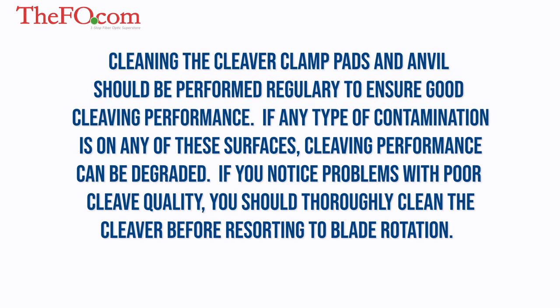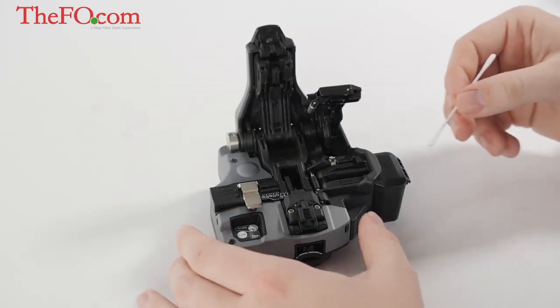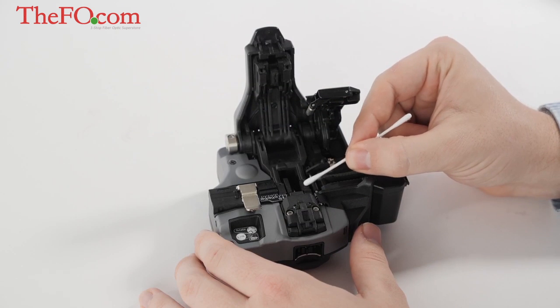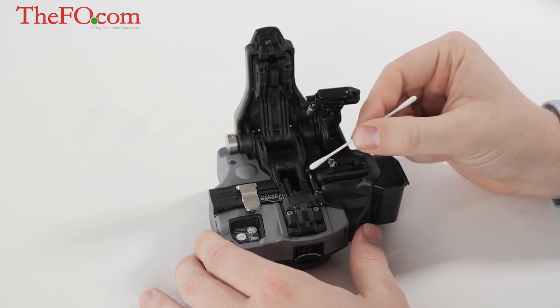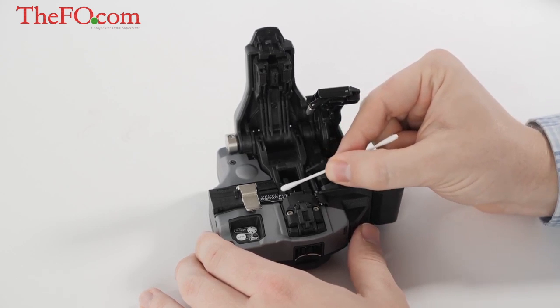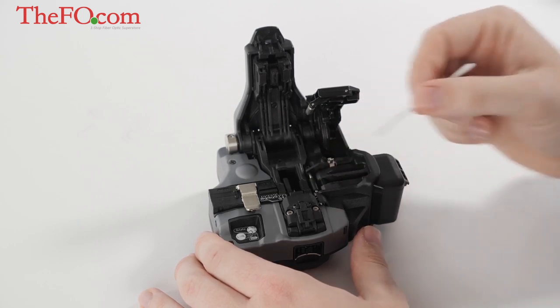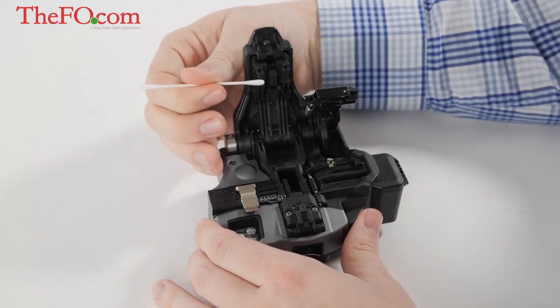Cleaning the cleaver clamp pads and anvil should be performed regularly to ensure good cleaving performance. If any type of contamination is on any of these surfaces, cleaving performance can be degraded. If you notice problems with poor cleave quality, you should thoroughly clean the cleaver before resorting to a blade rotation. Take a lint-free cotton swab, lightly moistened with 99% or greater isopropyl alcohol, and clean each clamp pad and the anvil. Rub in a back and forth motion to ensure you clean the entire surface of each item.